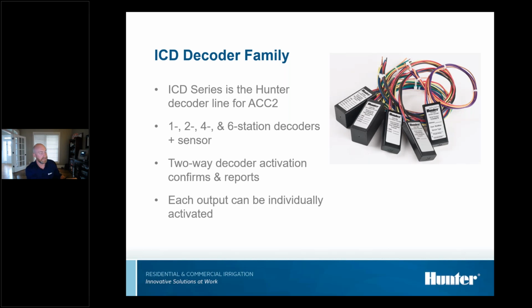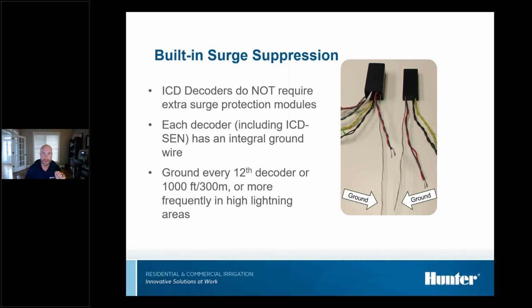One thing about the ICD is that they use 2-way communication. The clock sends out a signal saying station 17, I want you to turn on. Station 17 turns on and sends a signal back saying everything's okay, I'm operating just like normal. If this decoder happens to be bad, say it got hit by lightning, it won't send that signal back. The clock will know something's up and it'll throw a fault, making a record that's logged in the controller log. So 2-way communication - want to make sure everybody's on board with that.